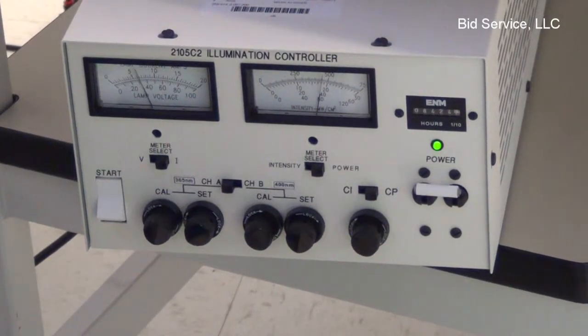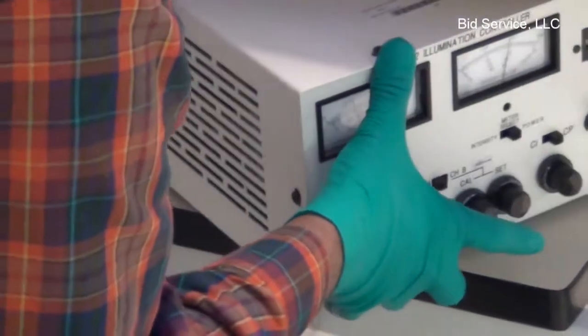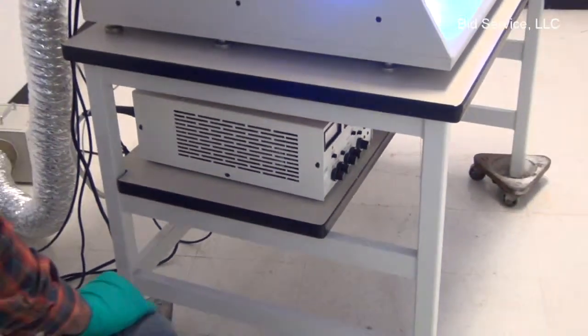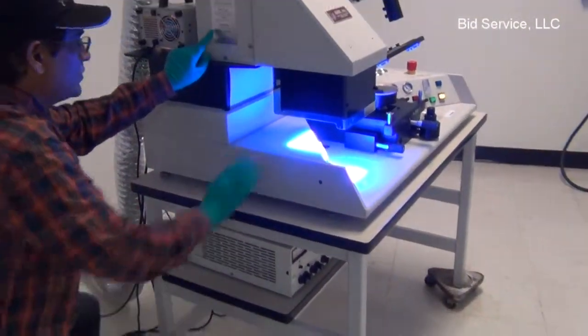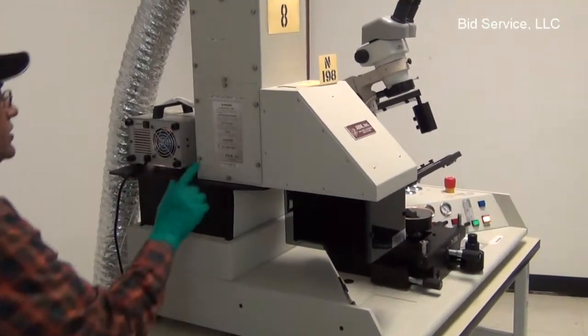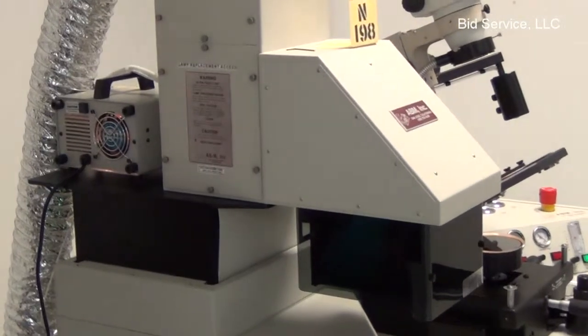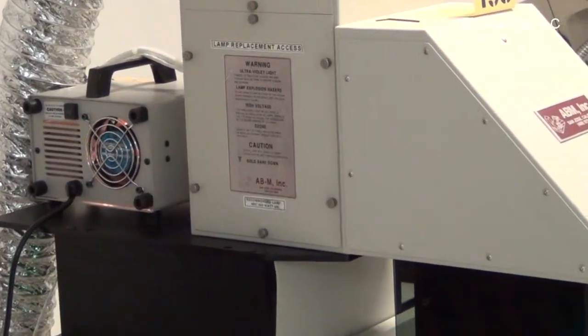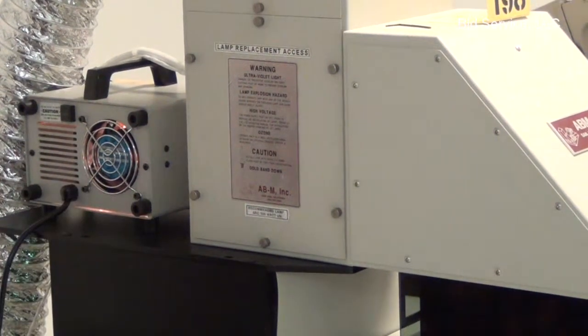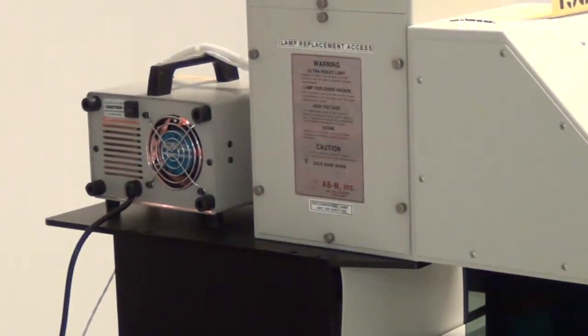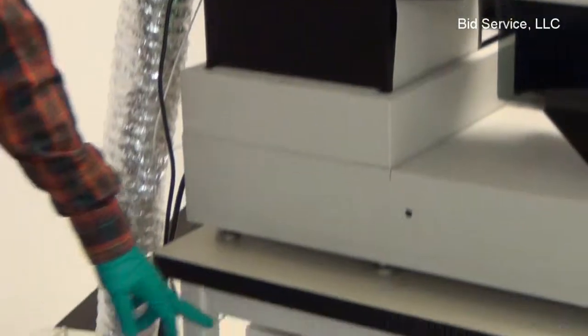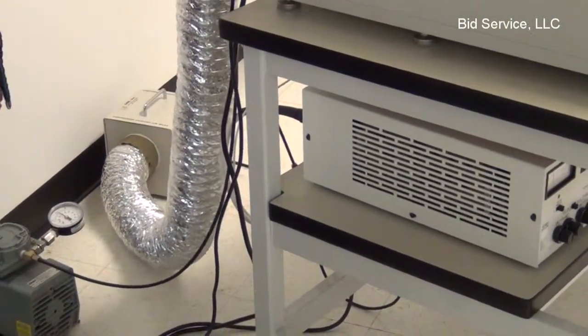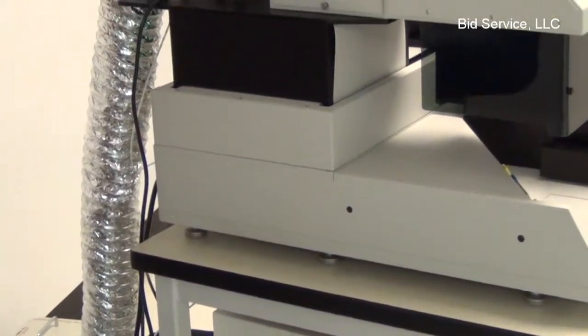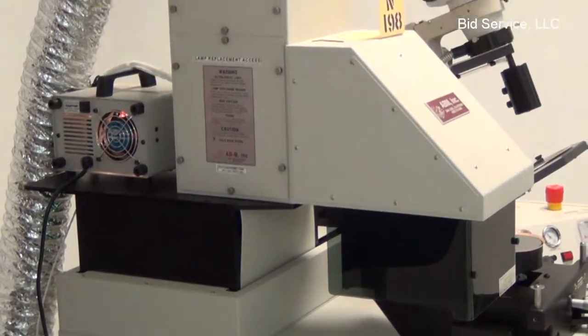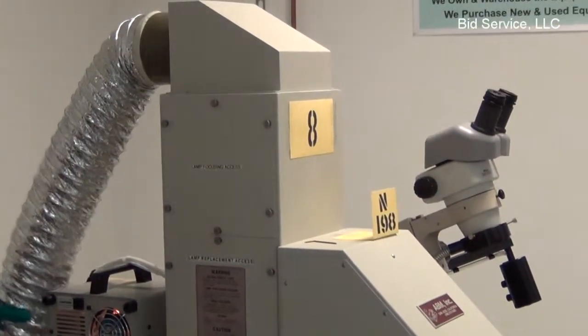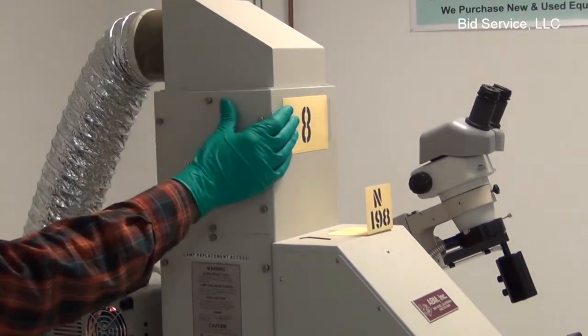The unit will be shipped with the lamp out of the lamp housing. The lamp, when it is to be installed, should be installed with anode in the down position. The anode is marked on the metallic electrode. There is the aluminum heat sink that goes on the anode. Before connecting the electrically, the heat sink should be used. The unit comes with an exhaust fan connected, which is powered from the lamp power supply, and there is no feedback mechanism to check if the fan is running. So the operator must verify the fan operation once in a while. Otherwise the lamp housing will get heated up.